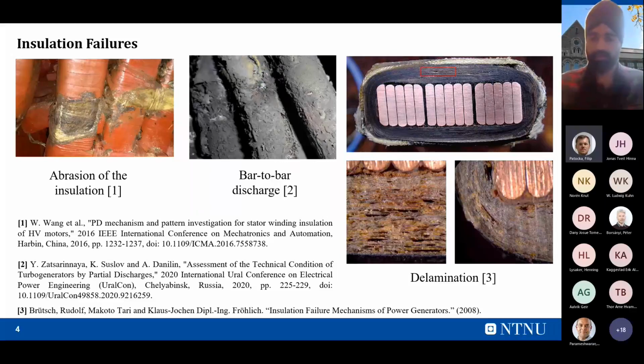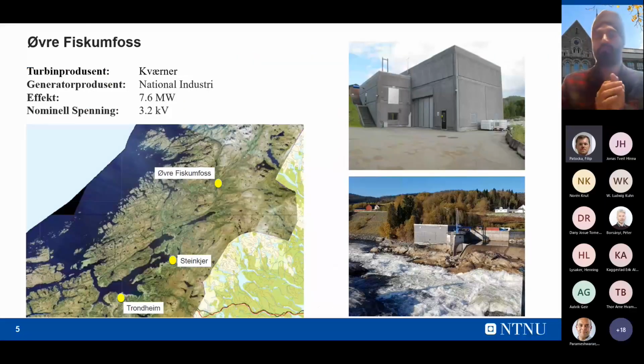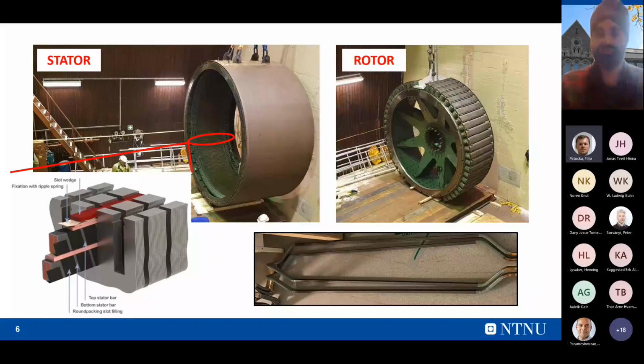For my study, there is a nearby small hydropower plant, which was commissioned in 1976 with a rated active power of 7.6 megawatts and a nominal voltage of around 3.2 kV. The turbine was manufactured by Kvaerner, and the generator was manufactured by National Industri. In the next slide, I'll give you some pictures to give an idea of the size of the stator, I mean the windings I'm going to use for testing purposes.